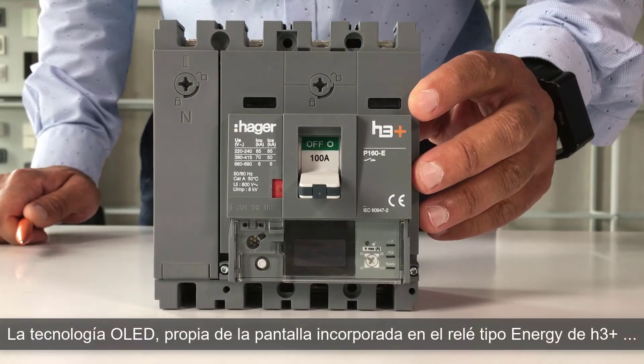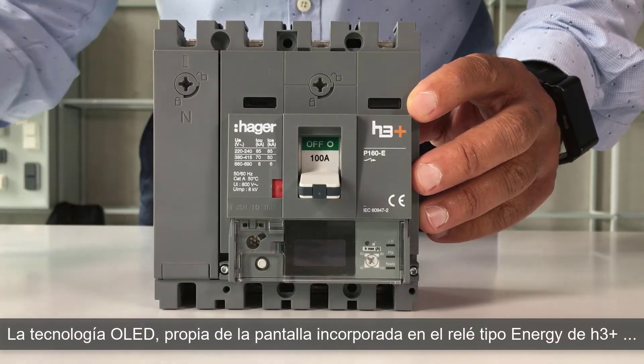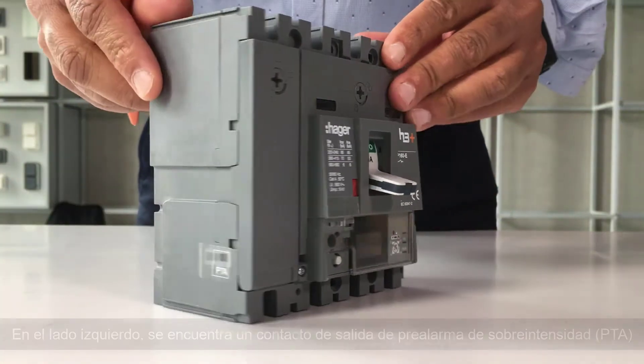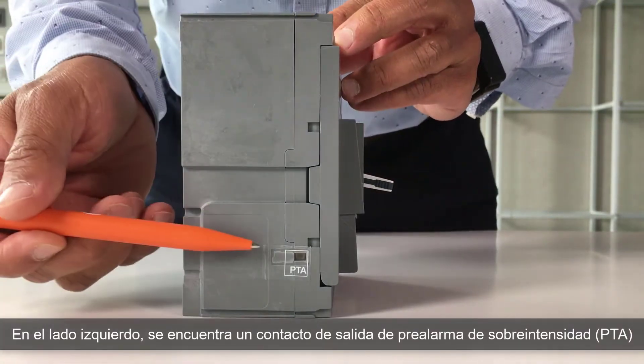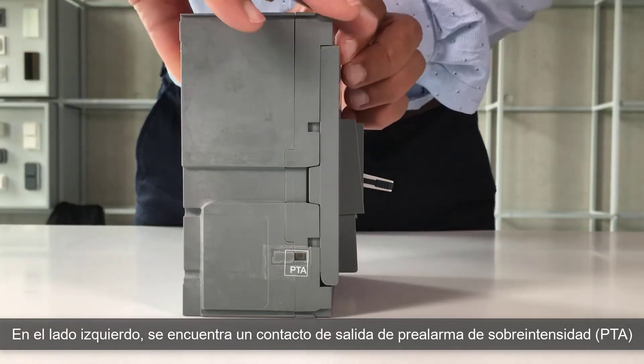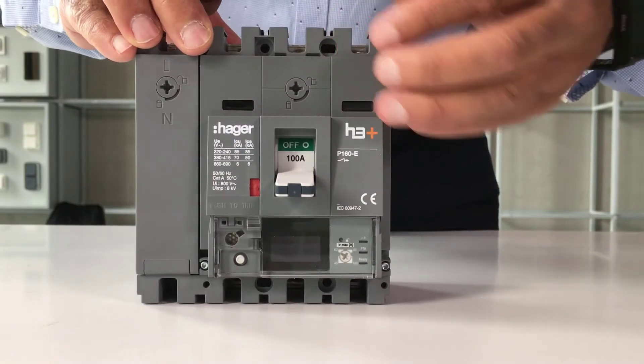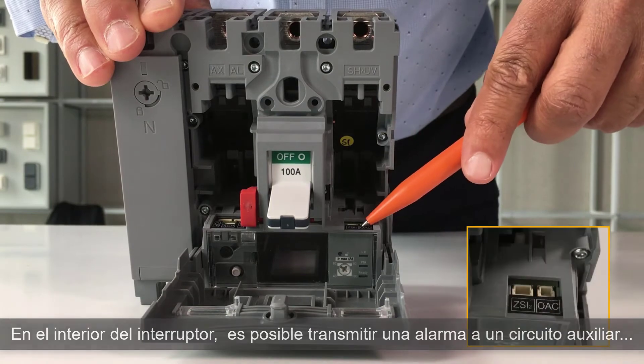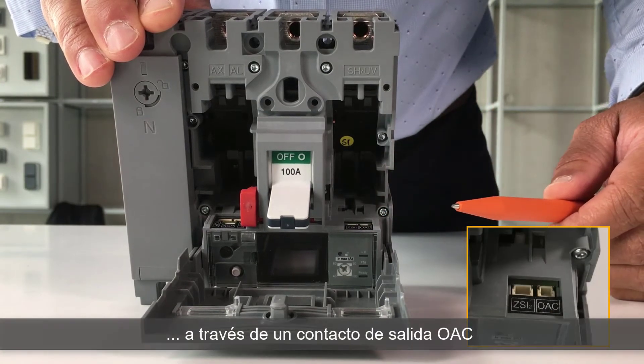The OLED technology on the embedded display of the H3 Plus Energy Trip Unit enables optimal readability. On the left side of the energy circuit breaker, you can find an overload pre-alarm output contact. Inside the circuit breaker, you can transfer an alarm to an auxiliary circuit using the OAC output contact.